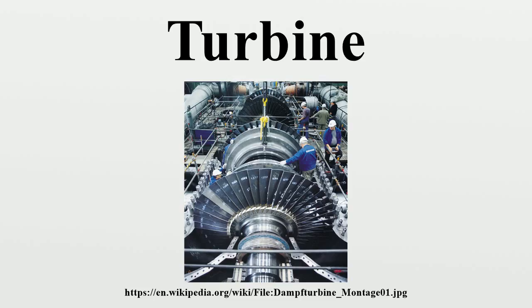Turbines with multiple stages may utilize either reaction or impulse blading at high pressure. Steam turbines were traditionally more impulse but continue to move towards reaction designs similar to those used in gas turbines. At low pressure, the operating fluid medium expands in volume for small reductions in pressure. Under these conditions, blading becomes strictly a reaction-type design with the base of the blade solely impulse. The reason is due to the effect of the rotation speed for each blade.